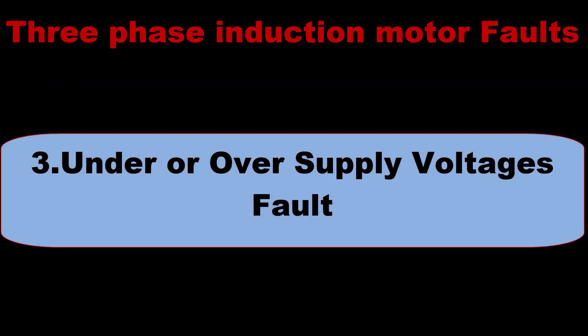Under or over supply voltage fault: this fault occurs when supply voltages are under or over a specific limit. The limit of three-phase AC supply voltages is 380 to 440 volts. When supply voltages cross this limit, the motor could be burned or heat up.